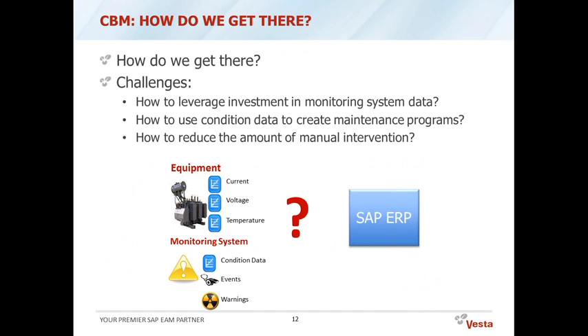You do not have to do the manual intervention. What does that mean? Rather than me running around every week with a temperature gun in my hand, I can simply put temperature sensors on the equipment if they're static and feed that information continuously into a monitoring system, which is then using Vesta CBM to inform the SAP ERP system and the maintenance team about possible events that might occur.